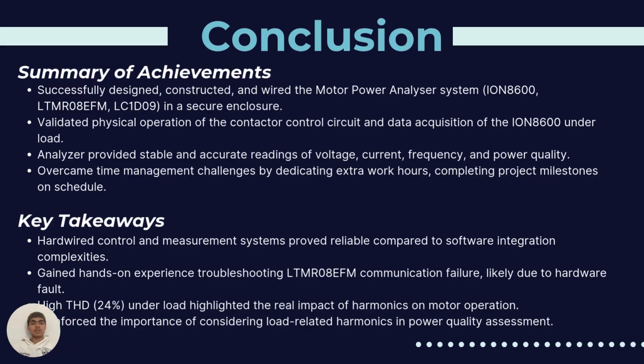Conclusions summary: successfully designed, constructed, and wired the power analyzer systems and the relay and the contacts in a secure enclosure. Yep. So every component we've got has an enclosure which makes them safe from any dust or weather differences. And the analyzer provided stable and accurate readings of voltage, current, frequency, and power quality. So by getting these accurate readings, the voltage, current, frequency, and power quality match our expected values, except the THD which is a little bit too high. And overcame time management challenges by dedicating extra hours, completing project milestones on schedule.